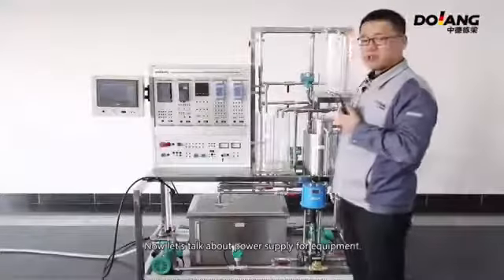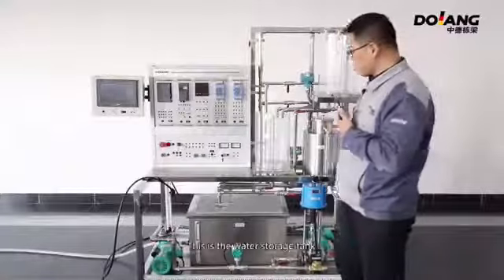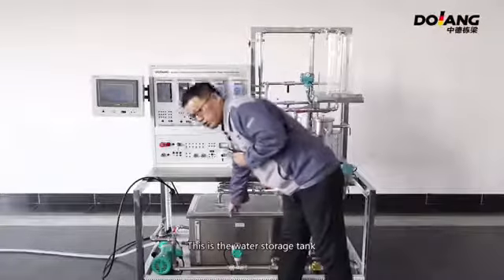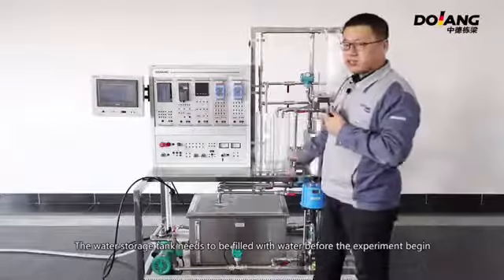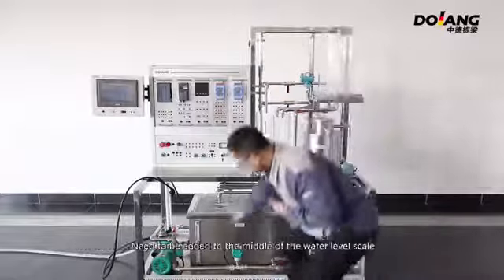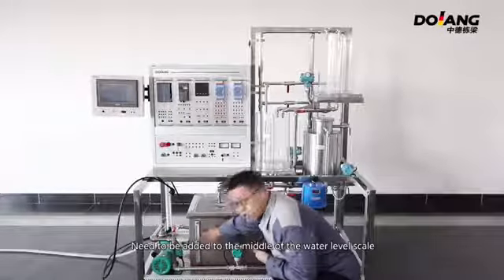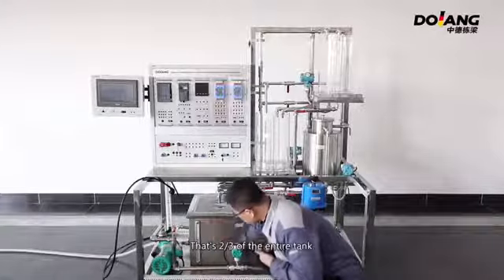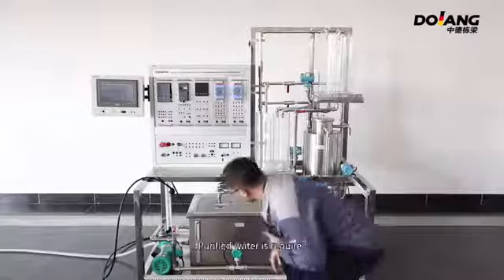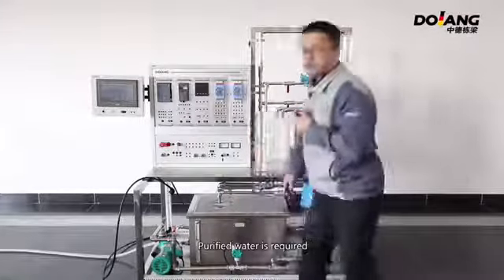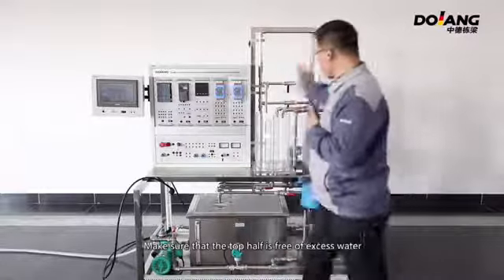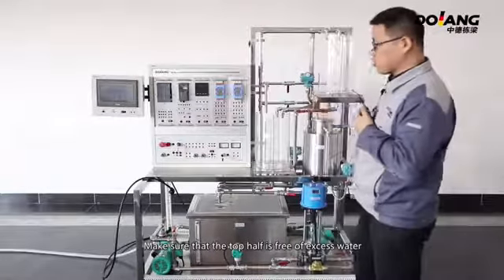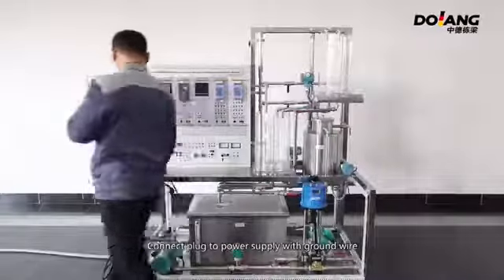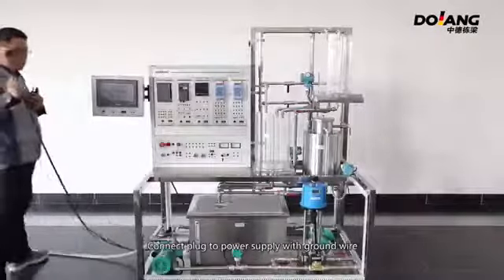Now let's talk about the power supply of the equipment. This is the water storage tank. The water storage tank needs to be filled with water before the experiment begins. It needs to reach the middle of the water level scale, that is 2/3 of the entire tank. Purified water is required. Make sure that the top half is free of excess water. Connect the plug to a power supply with a ground wire.